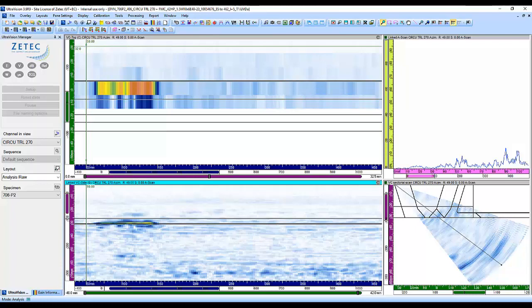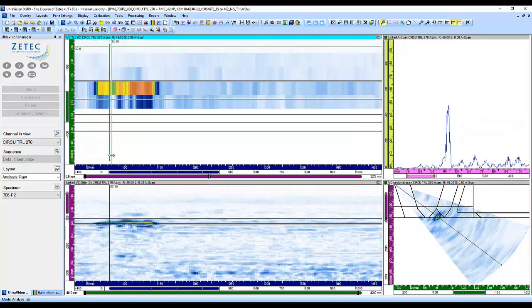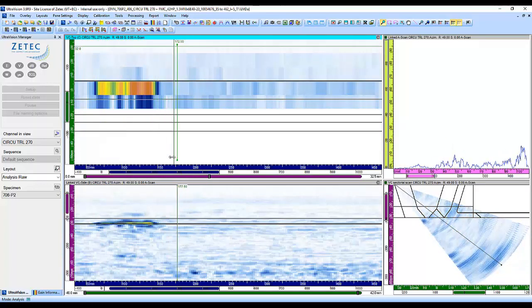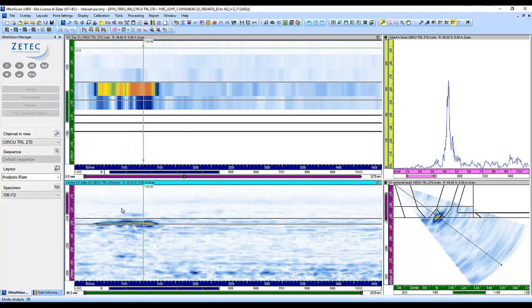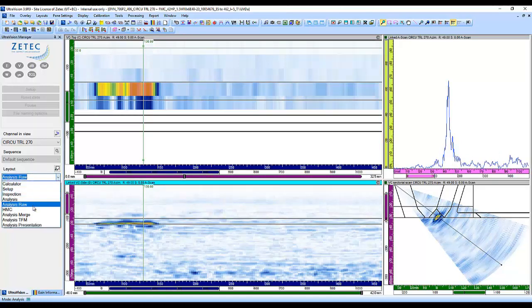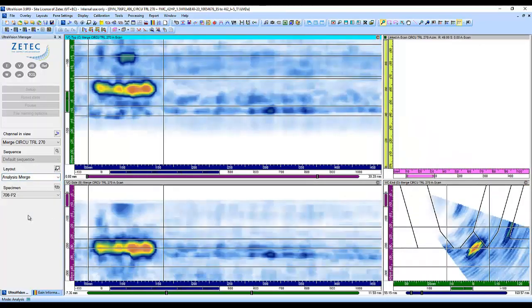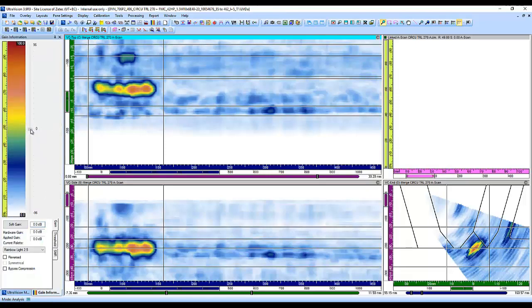We will use the UltraVision Classic software to review the data and perform post-processing of the raw FMC data with different advanced focusing algorithms. Here we see the standard phased array data, and when we move the data cursor to the zone of the flaw, it becomes visible on the sectorial scan and on the A-scan signal. The Volumetric Merge tool facilitates efficient data analysis and flaw evaluation, and this is how the merged data from the standard phased array looks.